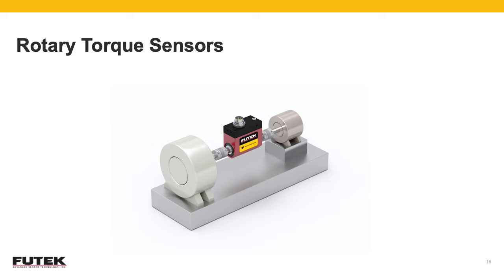Torsion measurement can successfully be monitored on a local digital display, also known as torque sensor indicators, such as panel mount displays, a handheld display, or connected to a PLC or streamed to a PC using a digital USB instrument. A rotary torque sensor transducer is also a crucial part of a dynamometer, or dyno for short, as it provides torque measurement and angular speed, which is RPM, to easily calculate output power, allowing accurate calculation of motor or engine performance in kilowatts or horsepower, as well as its electromechanical efficiency.